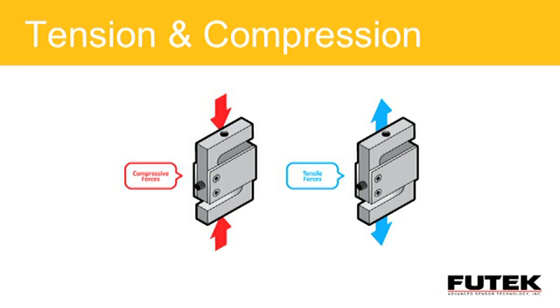These load cells are used in an inline loading environment, and they can measure both compression forces and tension forces, as shown on the right. It's fair to compare a load sensor to a common spring, a very stiff but repeatable spring. Like a spring, a load sensor will deflect either in compression or in tension, where it elongates when a force is applied to it.